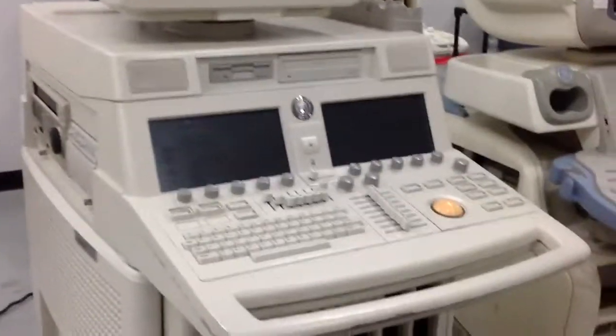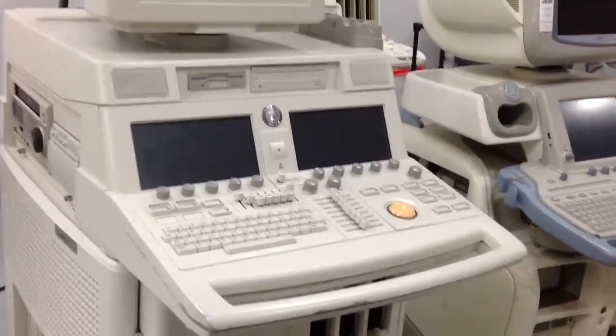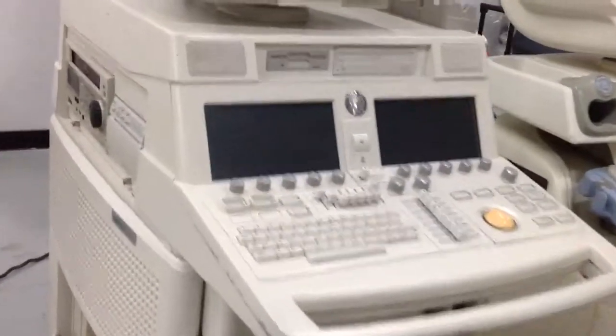I'm going to close it using one hand. Usually, you need to use both hands to do that. Once you close the system, you can power on the machine and test your ECG cable, to see if it is working or not.